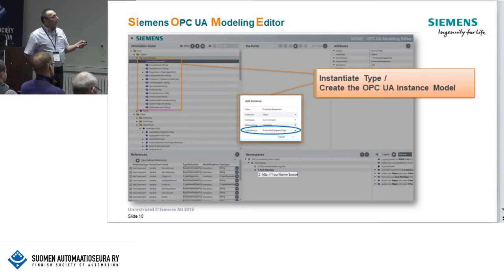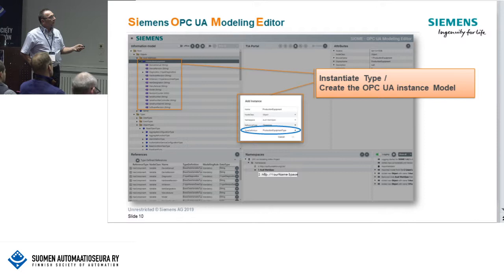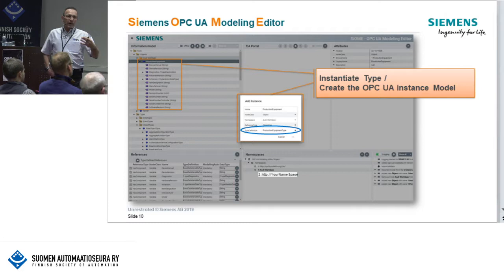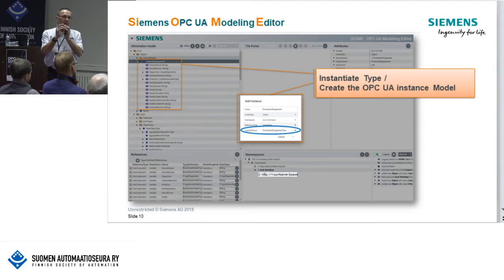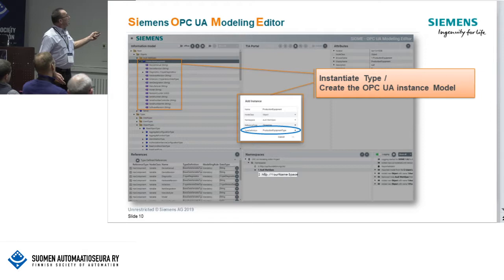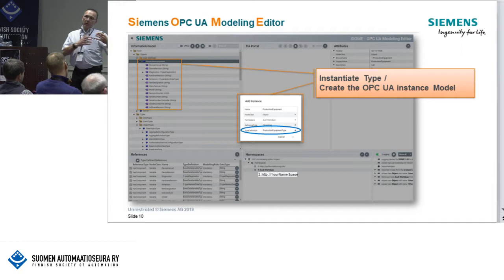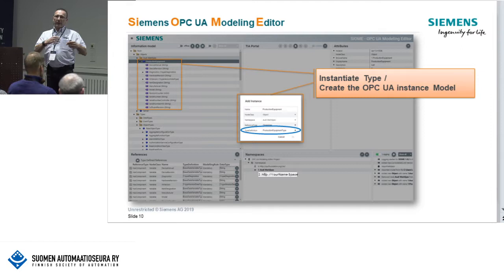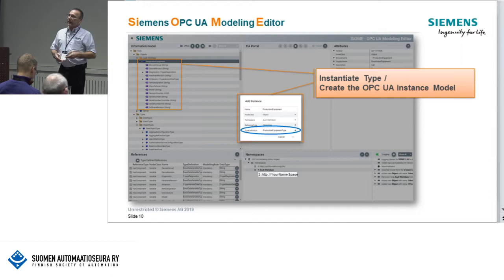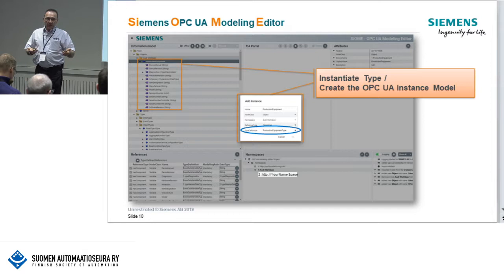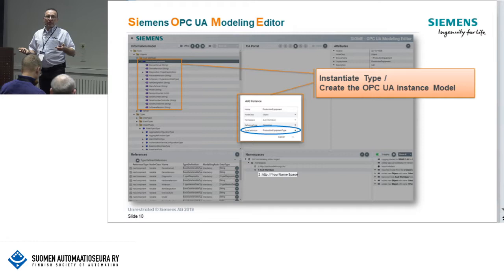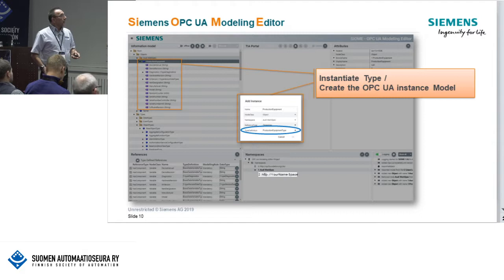When you instantiate a type in the instance model, you see a production equipment type and in the instance you see meaningful information about which type it is. A data client implementing this knows exactly what mandatory variables, properties, and methods to expect. You can prove with a client that if you implement it against a companion specification directly, the client can verify whether all mandatory elements are present, whether any are missing, whether the data types are correct — because all data types expected for a variable are defined in the type system — and of course which engineering units a variable or property has.